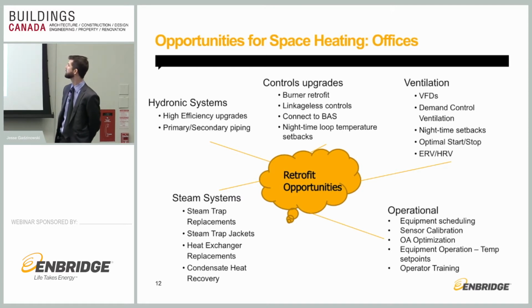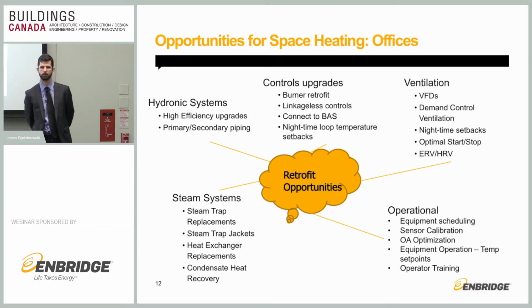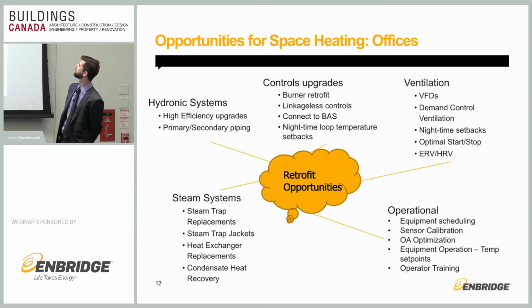And ERVs and HRVs. I've had a big project this year where we did around 34,000 CFM of incoming air. They put a couple of heat wheels on. There were 2 units, and I think they're saving upwards of 75% of the gas that would have been needed to heat up that incoming air just by having the heat wheel on there. So it's a good opportunity there as well. Although there are some challenges for sure in operations, because ERVs are prone to breaking down or being operated not optimally. So anyway, it's an opportunity. For steam systems, already went through that.